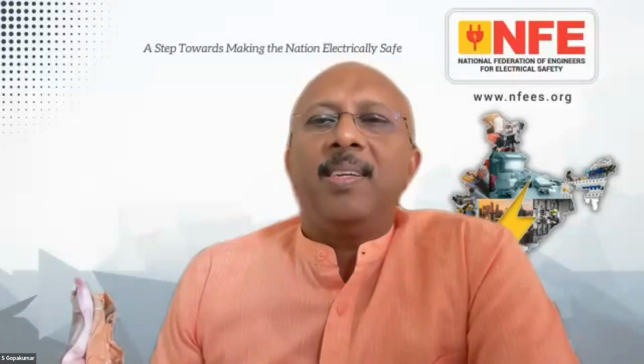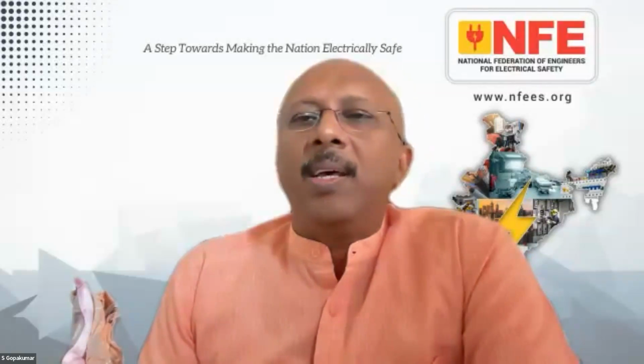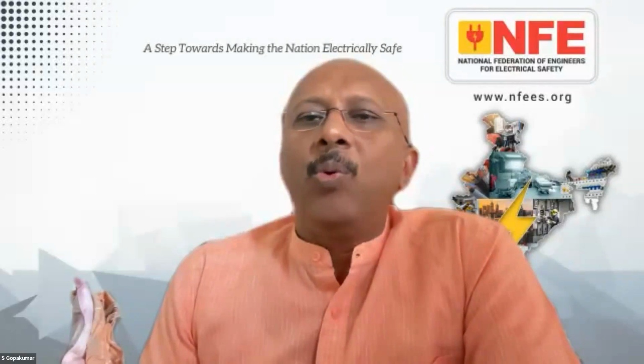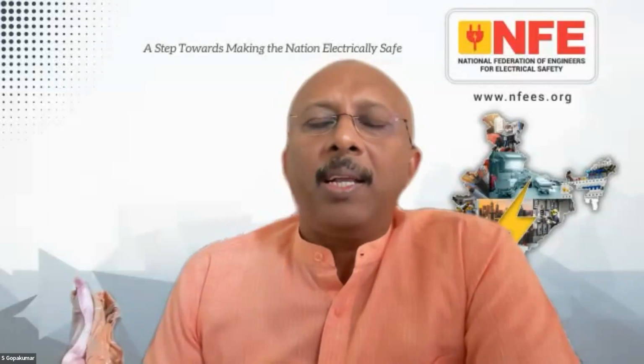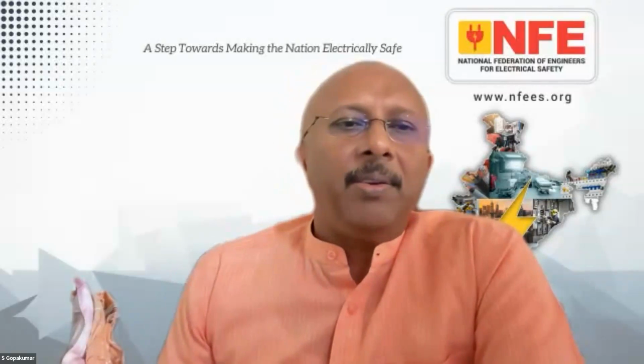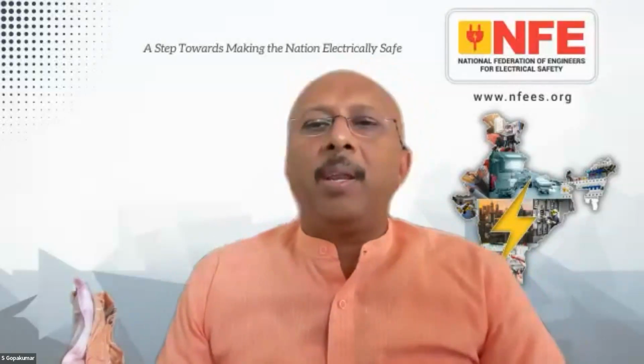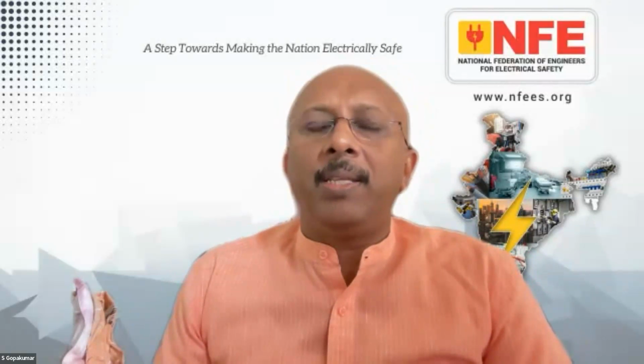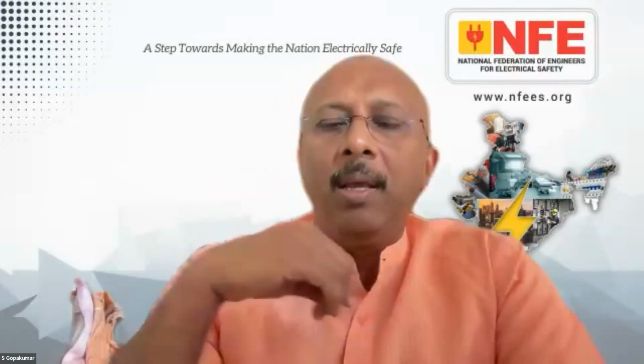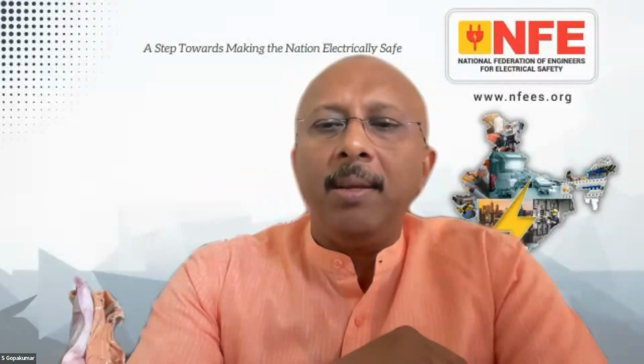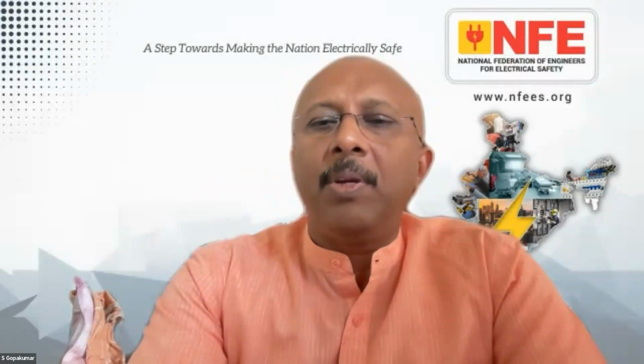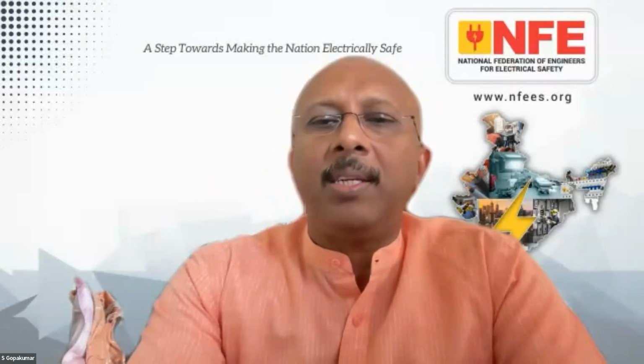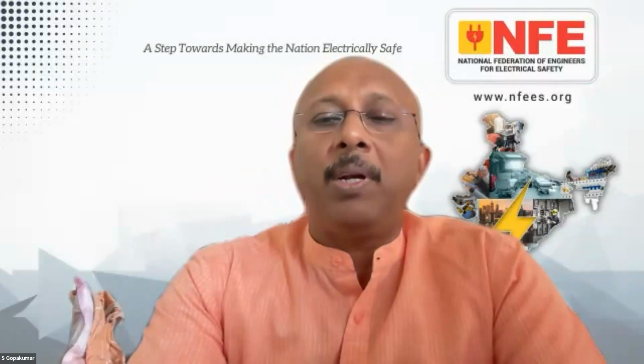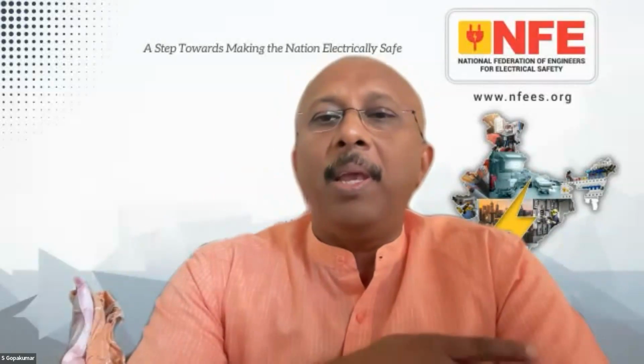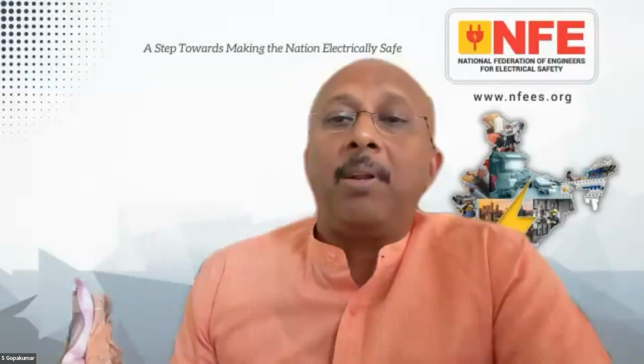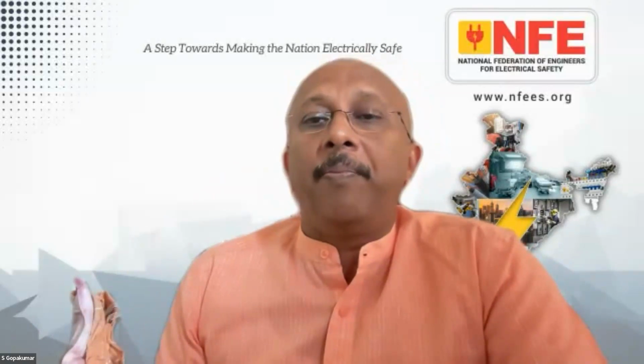Okay. There is one anonymous attendee asking how to identify the type of network. Actually, we have to make a verification. We have to make an inspection, or maybe make a test, and then only we can establish it. Also, please note that passing a fault loop impedance test doesn't mean that you have an efficient system, because sometimes there are connections made by mistake. As a result, the test may pass, but when there is a fault, it may create a fire in some part of the installation. So we have to make it proper.